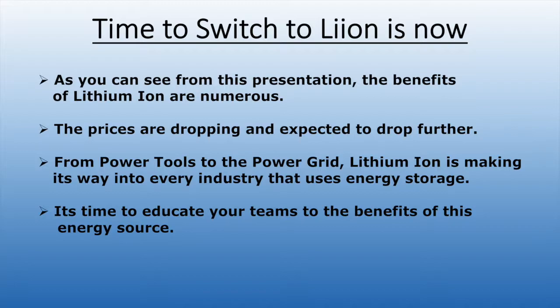There are two reasons they're more efficient. First, lithium ion has a lower series resistance. This is important because the higher the series resistance, the more energy is wasted. To achieve the same series resistance, a lead acid battery has to become larger and heavier. Second, lithium ion maintains a steady output voltage as it discharges, while lead acid voltage falls as it discharges. As the voltage falls, the load pulls more current from the battery to maintain the same output power. Remember we discussed VA equals power? Well, if V goes down, then A, current, must go up for the power to stay the same. More current means more heat and more wasted power. That means lithium ion is more efficient than lead acid.